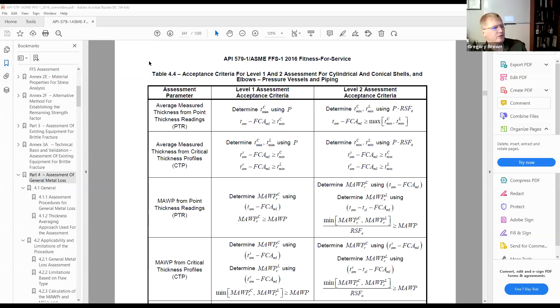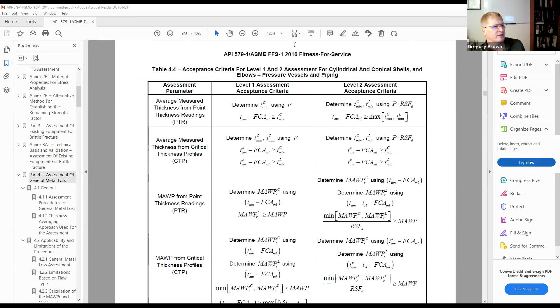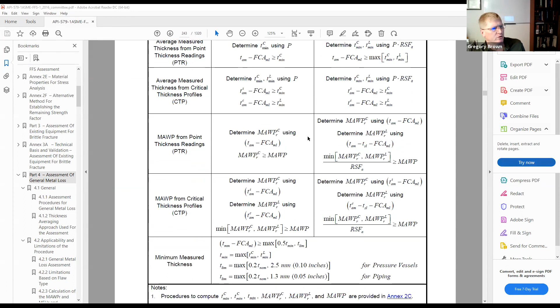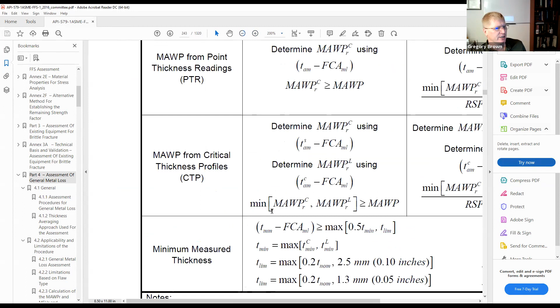So to answer your question, for example, if people can see that, I know this is probably a little challenging to see. This is from part 4 of 579. These are all the rules. We'll talk about these in the course. But at the bottom, you see that the minimum measured thickness has to be greater than this limiting value, what you're talking about. So you have to have at least half the design minimum or this limiting value, which you see is 0.2 of nominal. So 0.2 of nominal means I have 20% of my wall left, which means I've lost 80% of my wall. Does that answer your question?